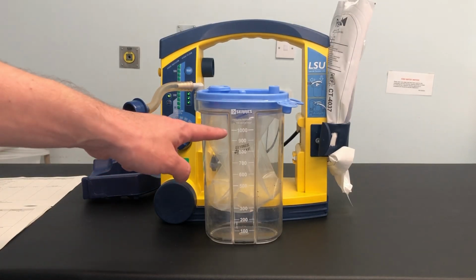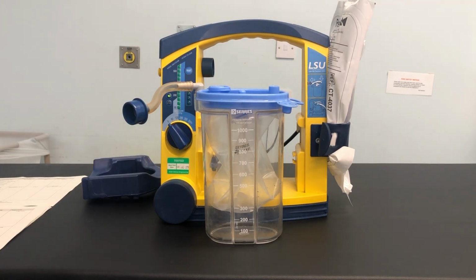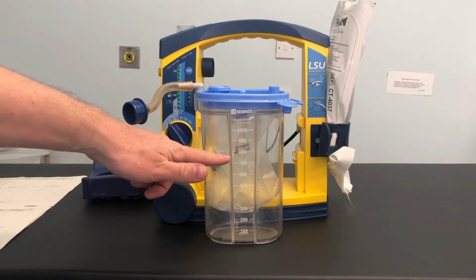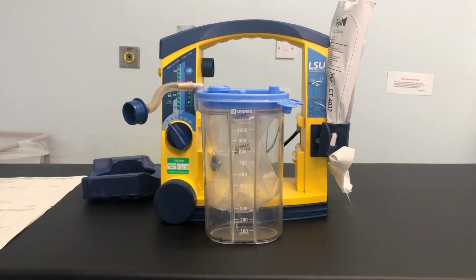Limitations and contraindications. The LSU is not suitable for use in the presence of flammable liquids or gases, as there could be a danger of explosion and or fire. The LSU is not intended for use in the MRI environment. The LSU is limited by battery life and canister volume. Battery life on battery operation is approximately 45 minutes at 500 millimetres of mercury, rising to 4 to 5 hours of intermittent operation, and the canister volume is 1,000 mils. However, it is recommended to replace the suction liner when it's about 3/4 full, approximately 700 mils, to reduce the risk of overflow of suction materials entering the device.